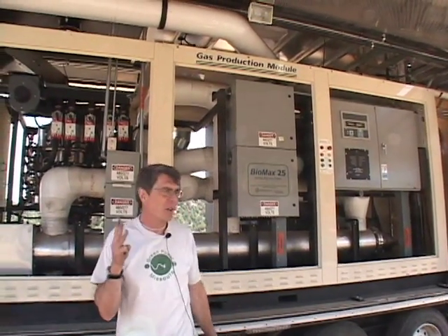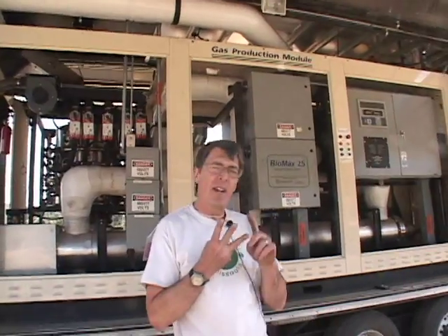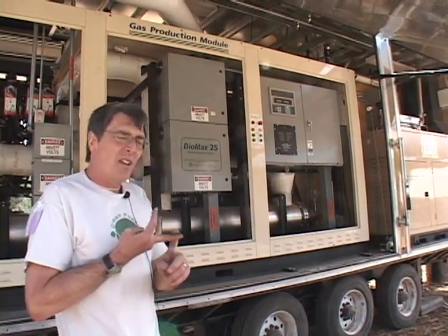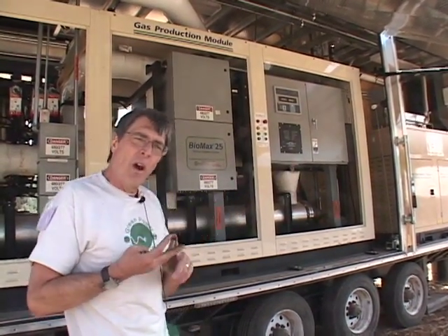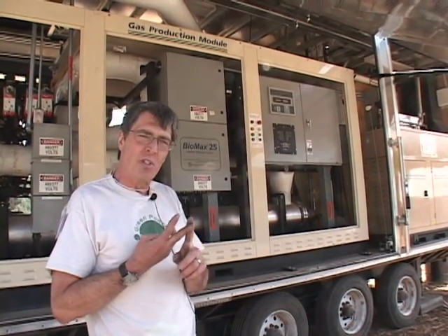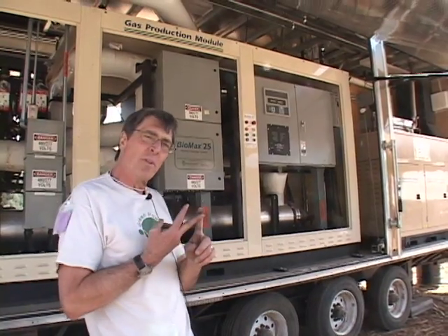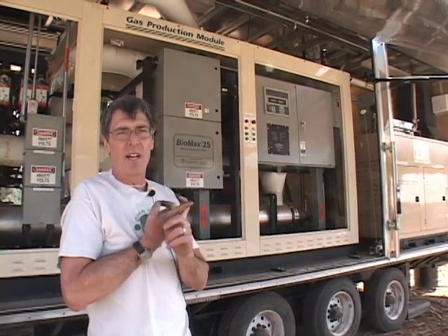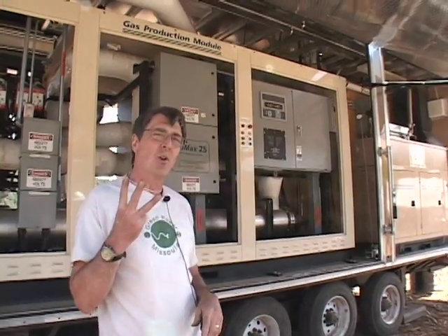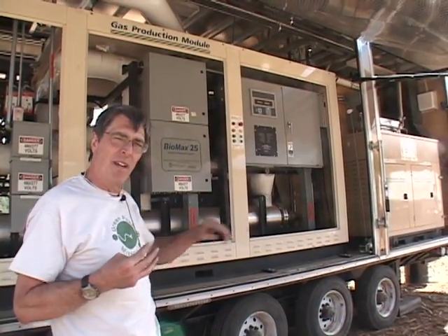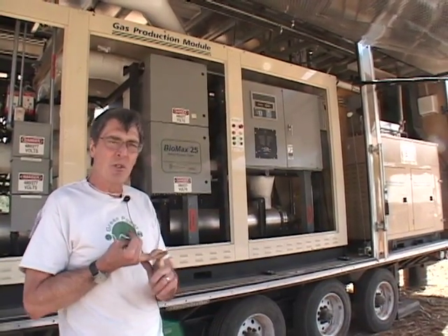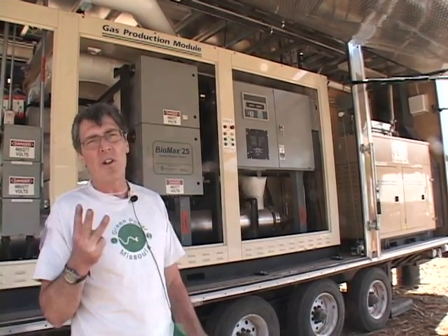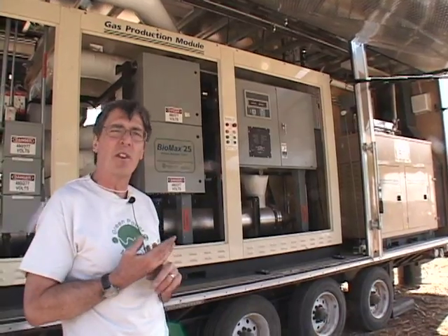We have three potential sources of recovered heat. First is the one I just showed you, this heat exchanger with the hot gas. The second one is in the engine compartment. We have a spark engine that's running over there. We'll show you that in a minute. There's also a heat exchanger in there, and I can recover heat off the exhaust gas. I can also recover heat off the coolant. So I have three potential sources. Right now I'm only recovering heat off the hot producer gas, and that gives me a thermal efficiency of about 70%. If I recovered heat from all three sources, that thermal efficiency would go north of 90%.